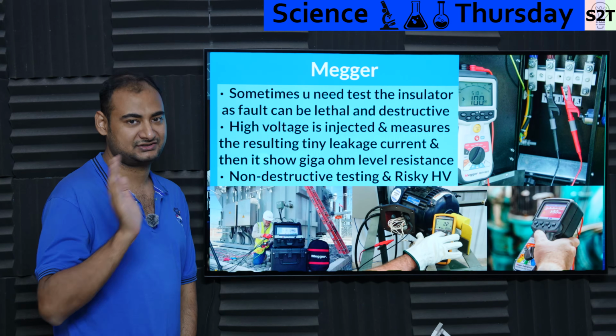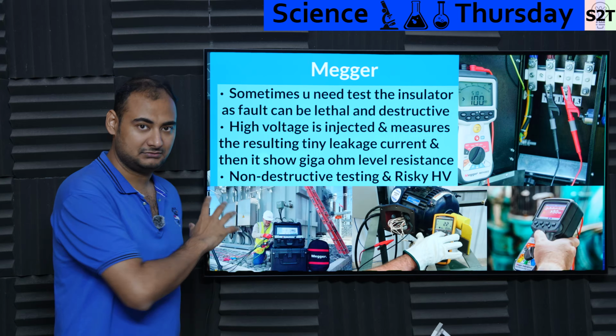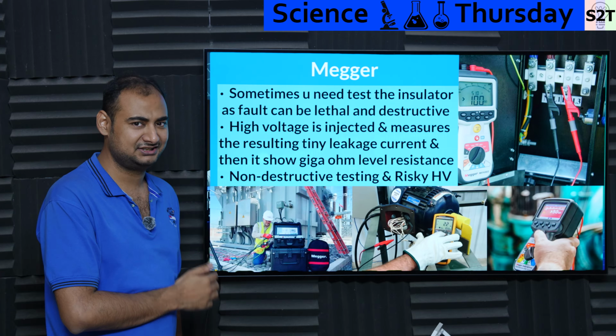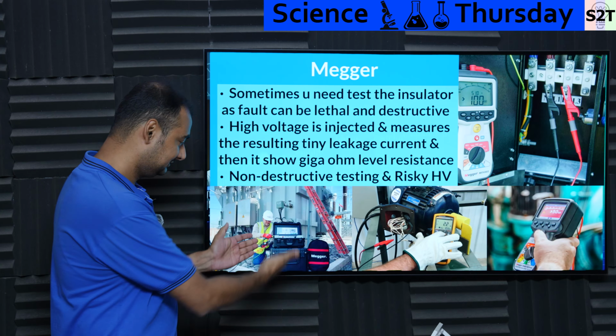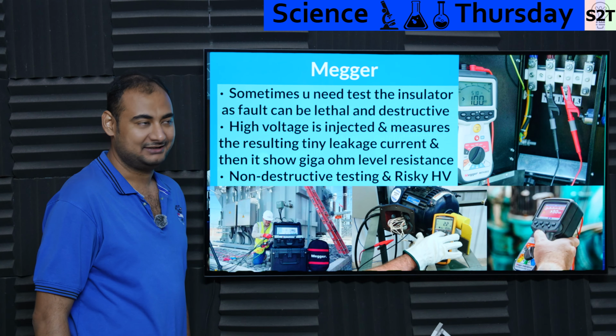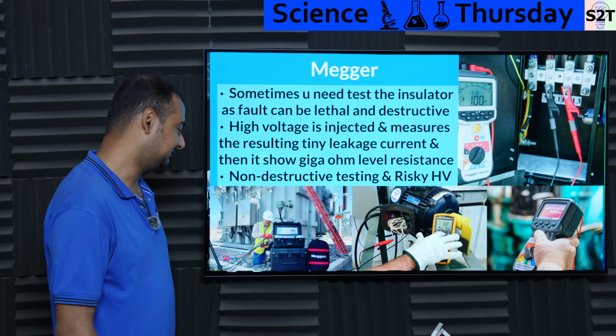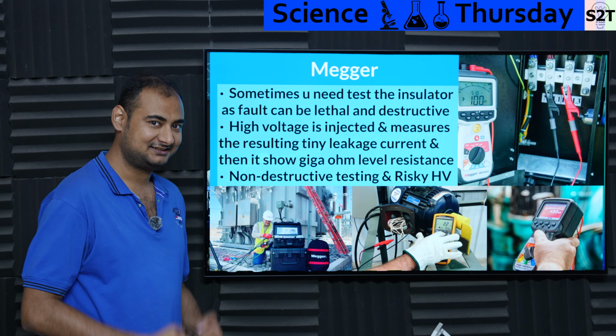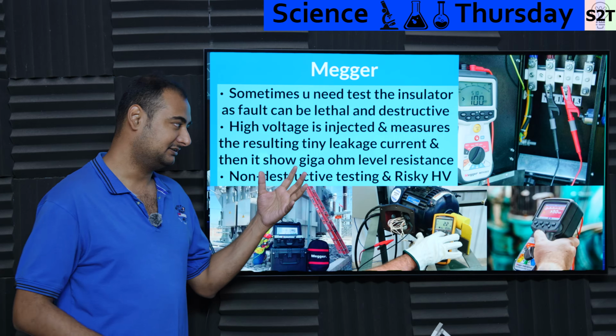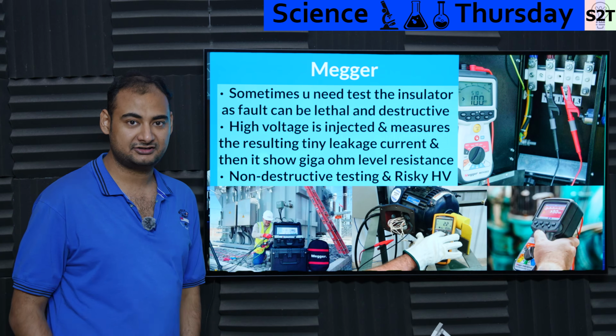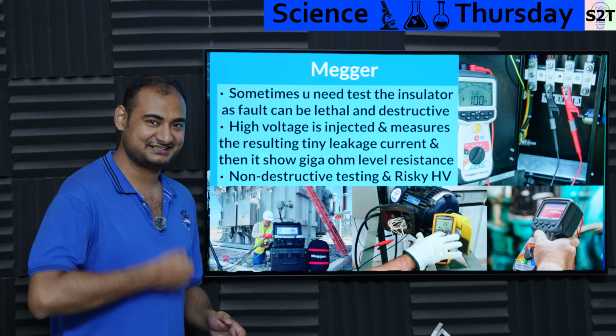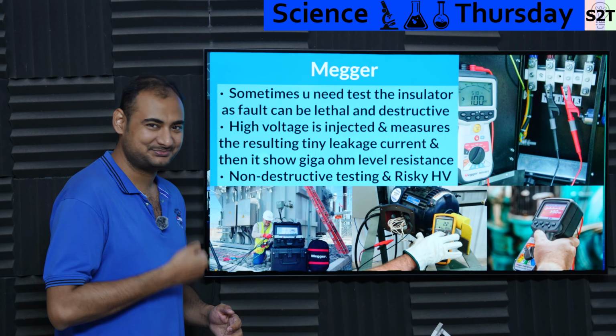Be mindful, gigaohm is extreme. Unless you're dealing with a substation transformer, you generally don't have to deal with that. But they come in these sorts of boxes and are ludicrously expensive for that exact reason. They have the oomph, the horsepower. Back in the old days when we didn't have reliable batteries, they had a hand-cranked generator, and you kept cranking that puppy up.